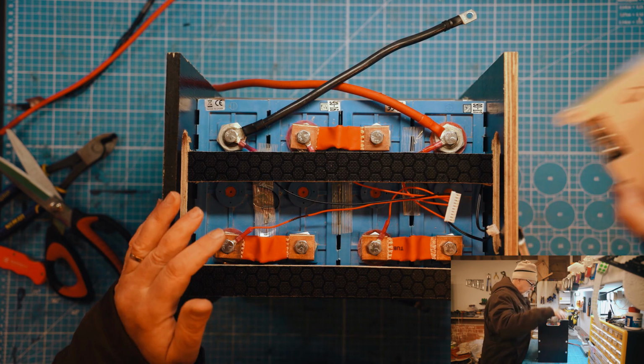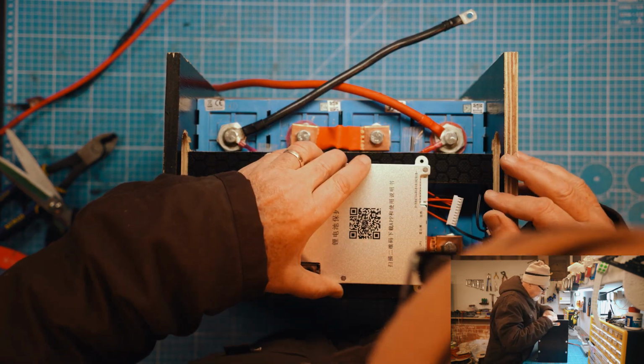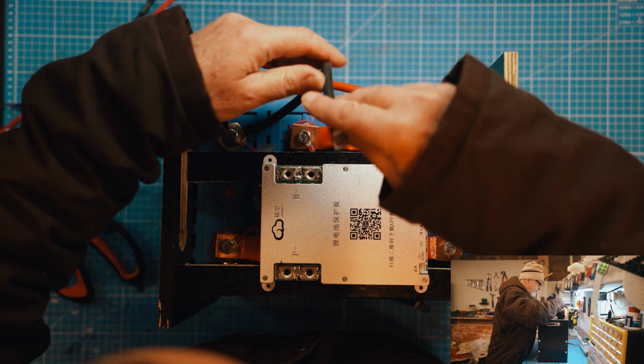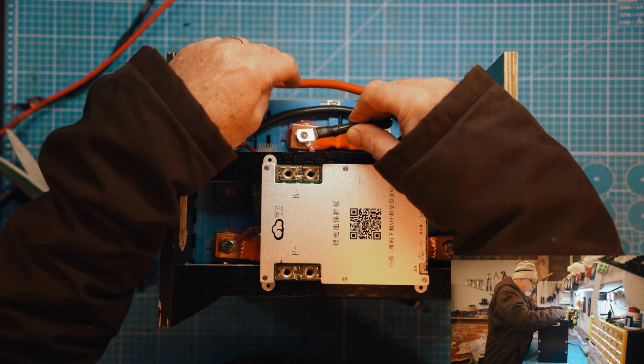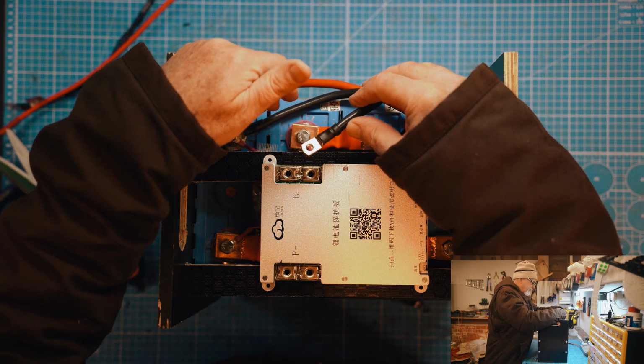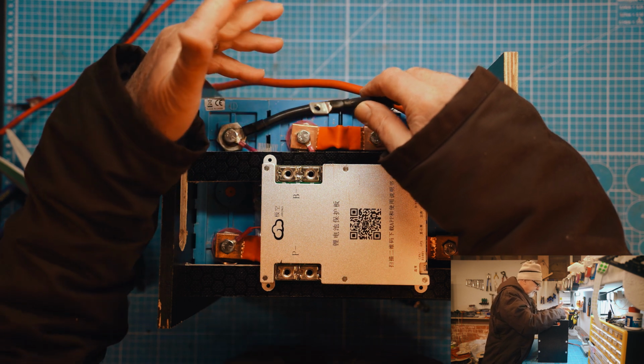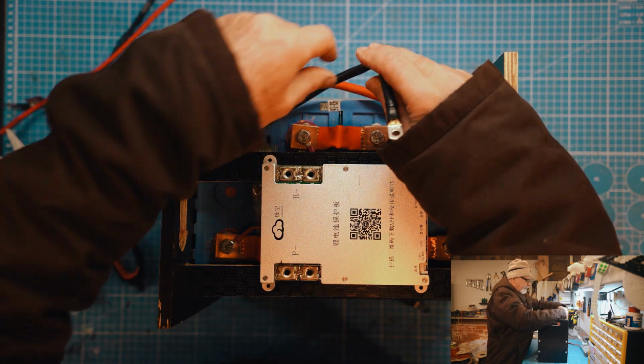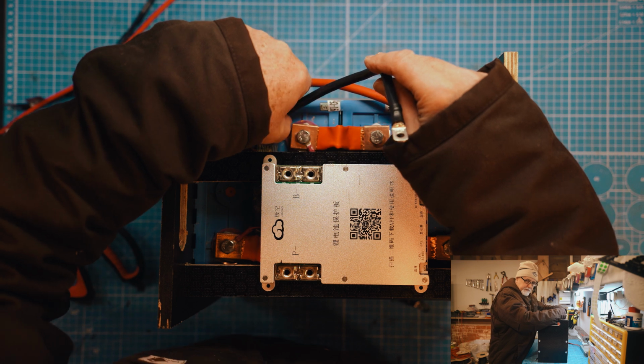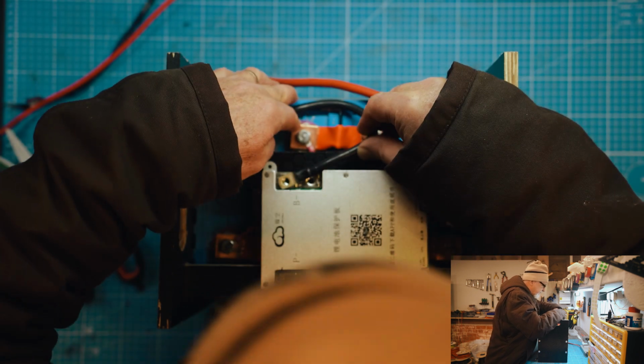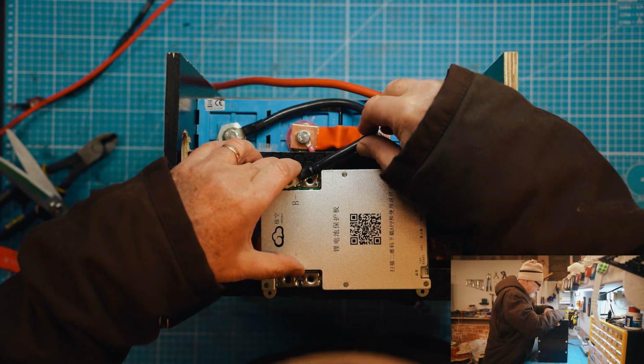Now we're going to mount the BMS right over here. So the main negative will come in here. The one thing that you should note is that there are cables that run across each other, and ideally you're going to want to put things like this into a conduit, but if I tighten it like this, that will not be making contact there. I'll move this out slightly so that there's no possibility of this rubbing against this sharp edge here and making contact. That should work fine.